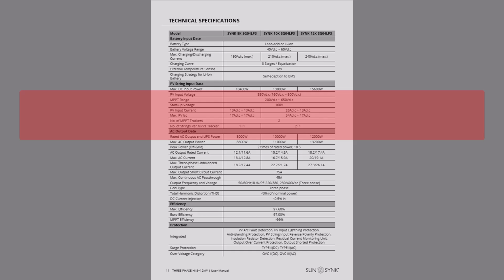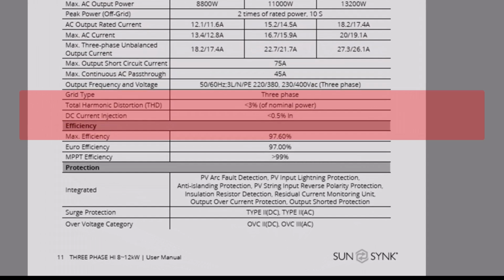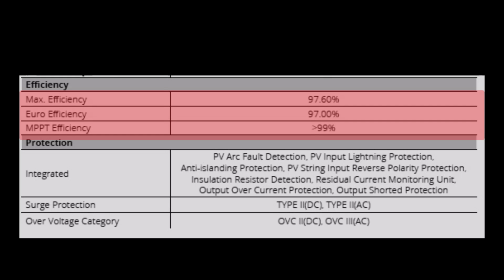Let's look at the efficiency numbers. The maximum efficiency of 97.6% means that this is the highest efficiency the inverter can achieve under optimal conditions.